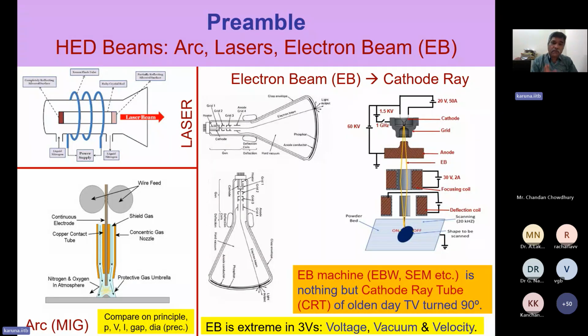Because you have to convey three forms of matter. You have to convey energy. Energy also goes in different forms. One is the high voltage energy. Then you send energies required for running the motor. Then the motors have encoders, so the encoder energy is in the form of pulses and signals. They are at low voltage, but they cannot be corrupted. So all that has to go through. This is quite a challenging task.